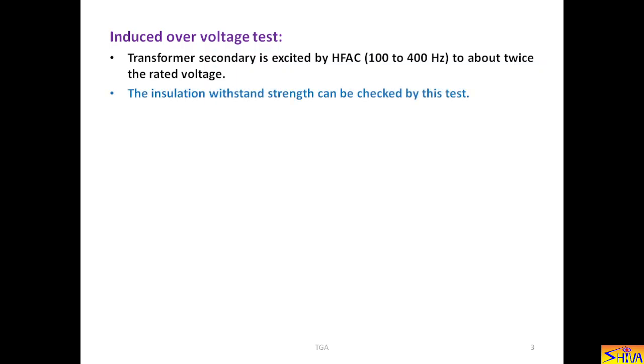Now, let us see what are the different tests performed on transformer. First is induced overvoltage test. Transformer's secondary is excited by high frequency AC in the range of 100 to 400 Hz to about twice the rated voltage. The insulation strength can be checked by this test.